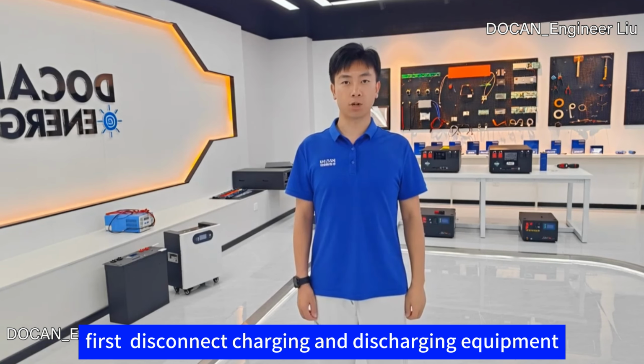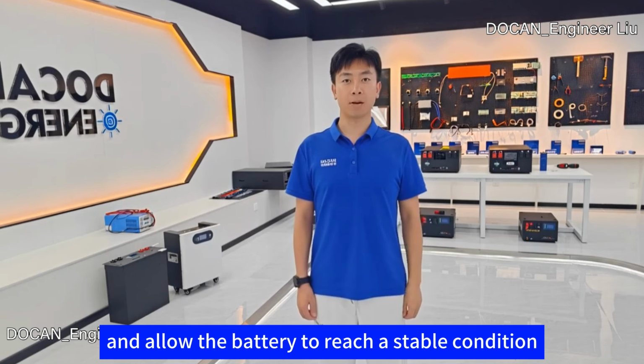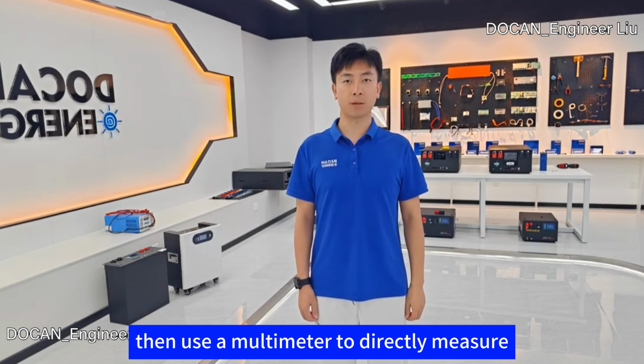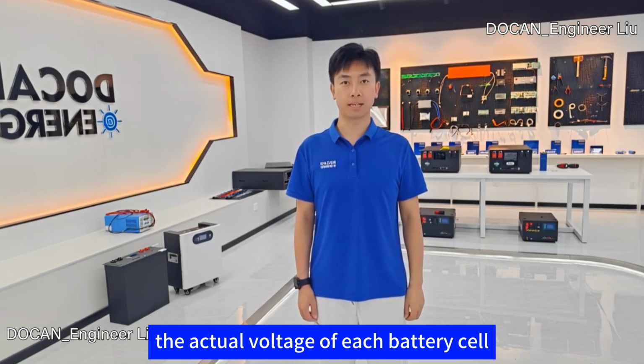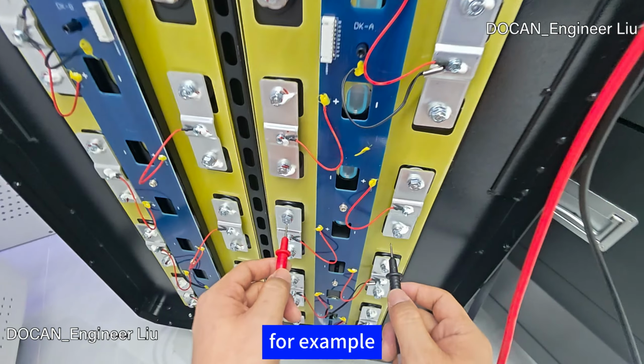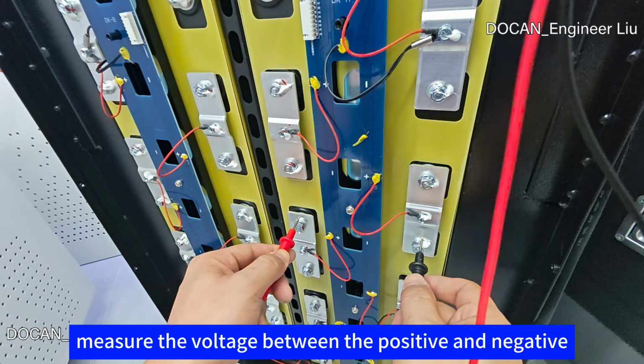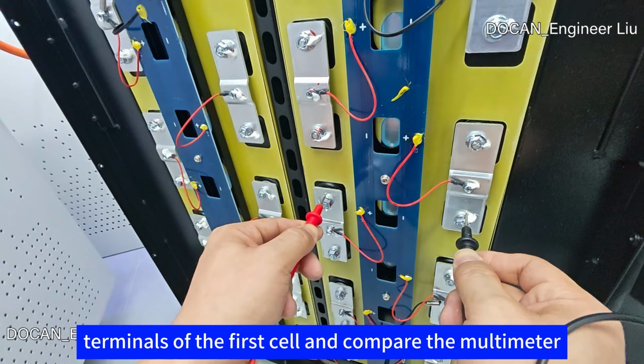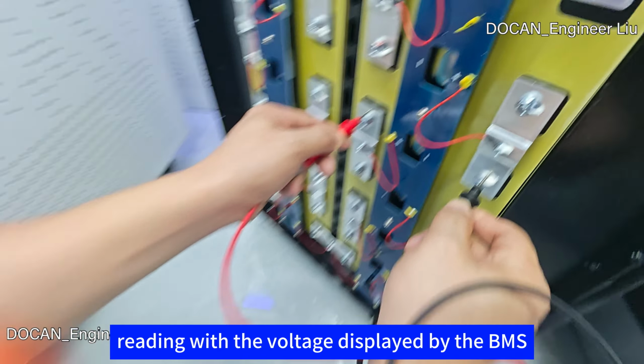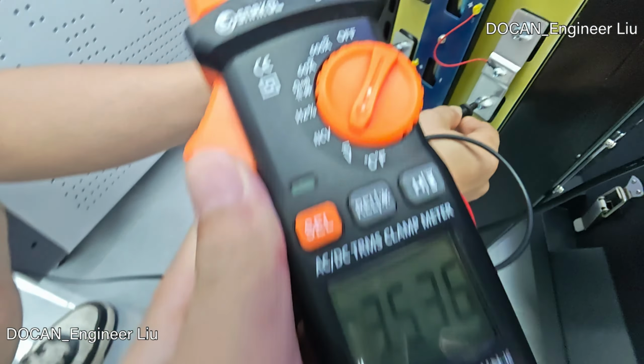First, disconnect charging and discharging equipment and allow the battery to reach a stable condition. Then use a multimeter to directly measure the actual voltage of each battery cell. For example, measure the voltage between the positive and negative terminals of the first cell and compare the multimeter reading with the voltage displayed by the BMS.